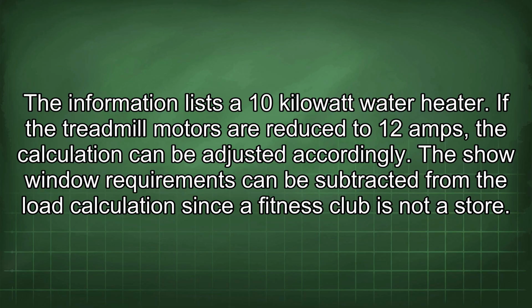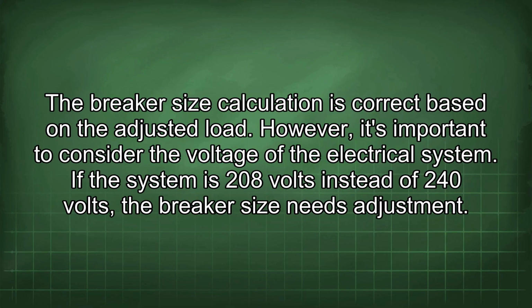If the treadmill motors are reduced to 12 amps, the calculation can be adjusted accordingly. The show window requirements can be subtracted from the load calculation since a fitness club is not a store. The breaker size calculation is correct based on the adjusted load. However, it's important to consider the voltage of the electrical system. If the system is 208 volts instead of 240 volts, the breaker size needs adjustment.